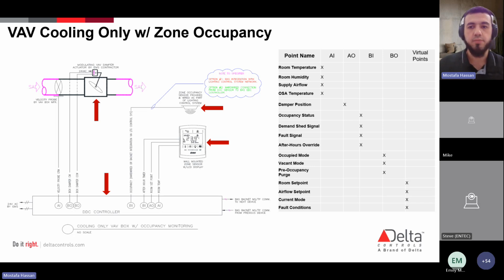There's your damper, right? So when the zone is in an occupied mode or an after hours mode, based on this occupancy sensor here, the VAV damper will be modulated to maintain a specific zone CFM setting. Okay, so that value will be set up, unless vacant mode has been triggered. So unless this occupancy sensor doesn't sense anyone in the space, then the damper will probably close to a minimum, right? Again, those are based on standards that Emily referenced yesterday. There are standards that don't allow you to really close the damper fully, because there's a minimum amount of airflow that has to be flowing in the space.